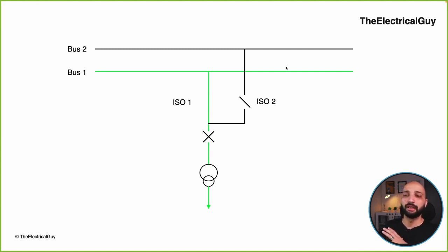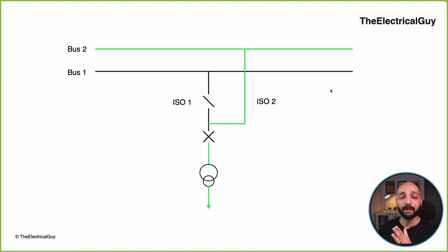Now, let's say there is a fault on bus 1 and bus 1 is not active. So in that case, to maintain the continuity of the supply, we can open isolator 1, of course after the opening of the circuit breaker only, and close isolator 2 so that bus 2 will be made active and supply can be taken from bus 2. And this is nothing but the rerouting of the power. We just rerouted the power from bus 1 to bus 2, and that can be done with the help of isolators. Now you can say this can be done with the help of a circuit breaker also.